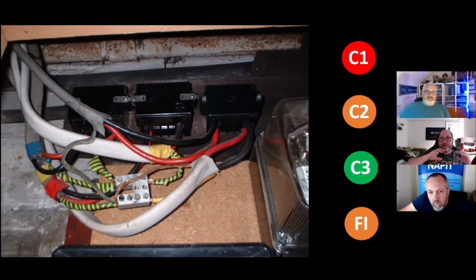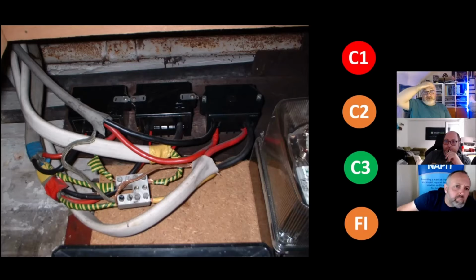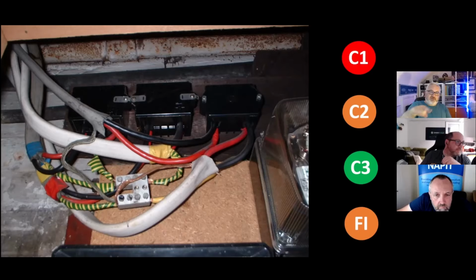Is this high up, out of the way? Yes, it's at the top of the storage. Is that the meter there, or is that a timer? That's a meter, which was for the shop premises. The three-phase supply was below that. There was some more switchgear, but this was the interesting bit that got sent to me, and the minute I saw it I was mesmerised by it. I went, what the hell is going on there? I was literally told this is being used to joint the supplies for the flats above.